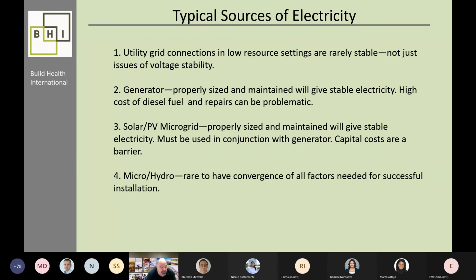Typical sources of electricity, the utility grid in low resource settings are rarely stable. And again, this isn't just an issue of voltage stability. Frequency changes really create havoc with big motors and really limit their life. And surges and spikes also affect the computers, the PLCs that run PSA plants. We see a myriad of issues with touchscreens on PSA plants losing their memory or losing the programming. Often those have to be sent back to the manufacturer to be reprogrammed.